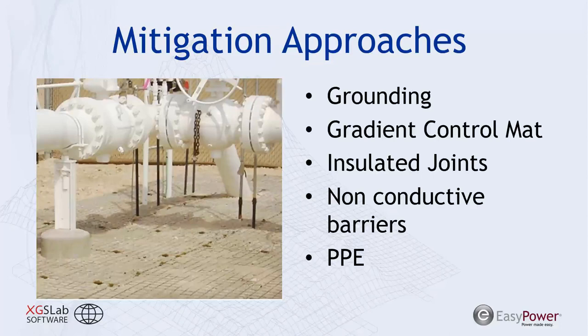Now, a lot of these are different mitigation options. Many of them are not applicable for all situations. You're limited by the operational practices or what's allowed by the recipient or what's allowed by the transmission line. And you may not have complete adherence implementing something like PPE, especially if at one pump station they need to wear electrical gloves and at every other pump station they do not. It's important to think of those real-world practices and incorporate that into any mitigation design.